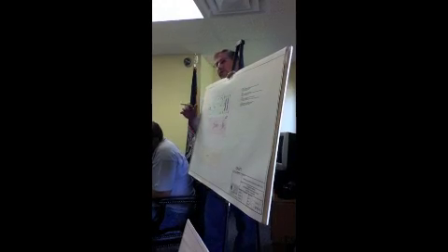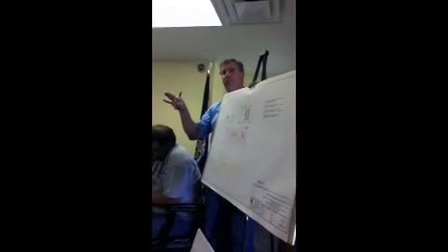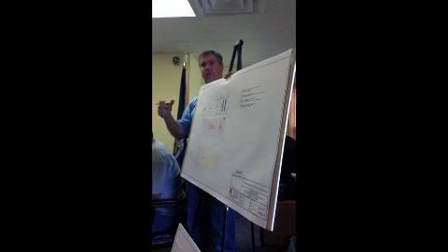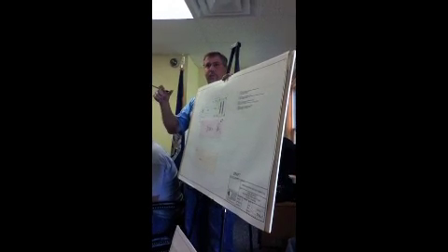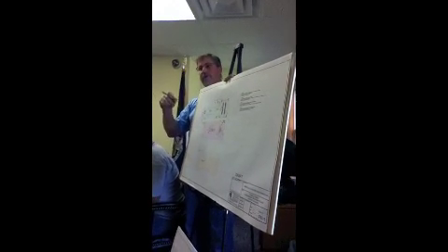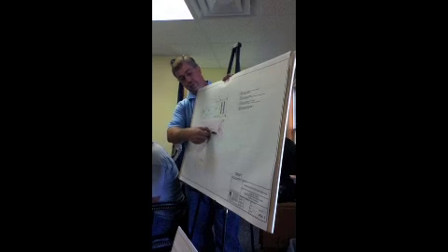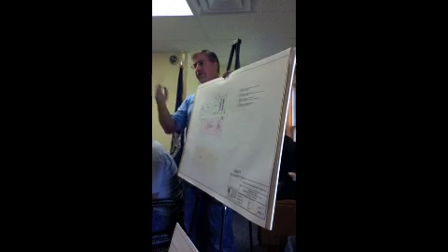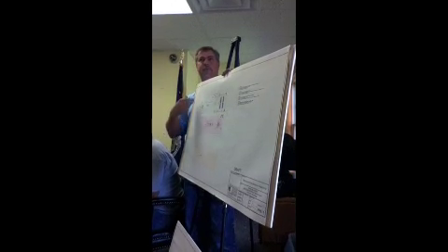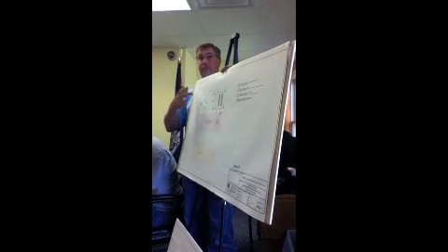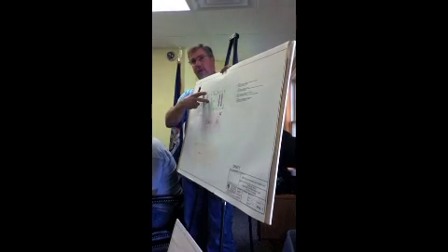Well, typically in a flood situation where he has most trouble now, because of the MEMCOR units, which are the microfiltration units. As soon as the water gets turbid going to them, because these units are pushed, the SBRs that are there now are pushed. Once the turbidity increases, the backwash increases, which doubles, sometimes triples his flow to the head of the plant.